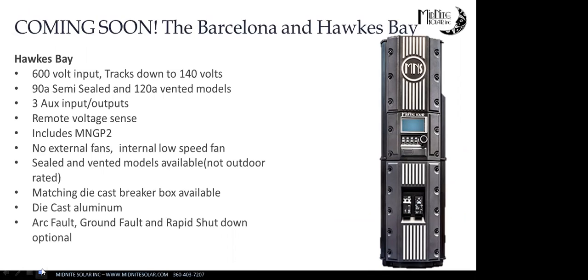So I'm going to talk about the Hawke's Bay first. The Hawke's Bay is a 600-volt MPPT charge controller. It will track all the way down to 140 volts. It comes in 2 flavors. It comes in a 90-amp semi-sealed unit. And when I say semi-sealed, I mean don't put it out in the water or underwater or anything like that. It's not physically sealed with gaskets or rings. It's just sealed up, kind of not quite as good as the old FX inverter, but close. And then it comes in a 120-amp vented model. They both have 3 auxiliary input outputs. They also have remote voltage sense for the battery bank.